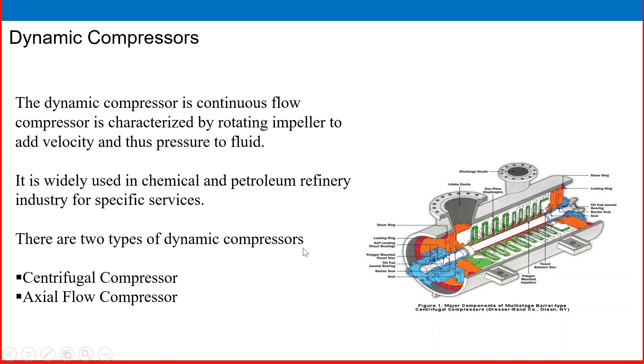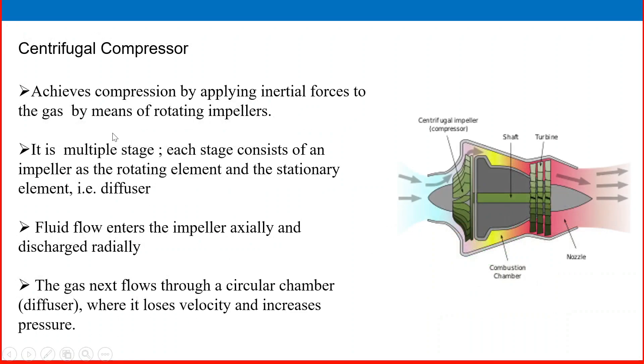It is widely used in chemical, petrochemical, and petroleum industries for specific services. There are two types of dynamic compressor: centrifugal and axial flow. In a centrifugal compressor, compression is achieved by applying inertial force to the gas by means of a rotating impeller. Each stage consists of a rotating impeller and a stationary element called a diffuser.